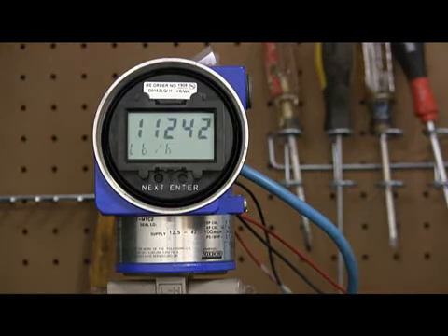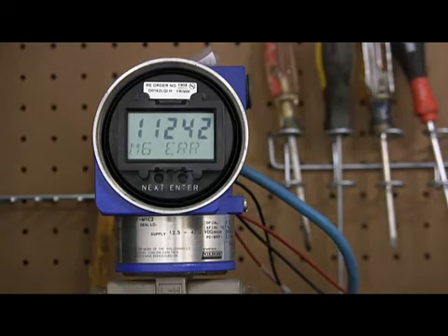M6 is the flow measurement. That means that the flow calculation may be an error. What would cause that message? Well, that message occurs when one or more of the process variables is outside of the user configured equation limits.